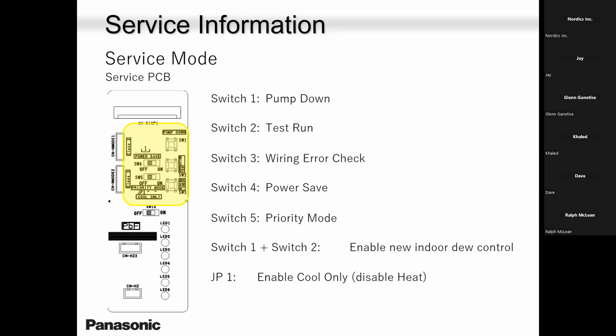Never put the unit in heat mode and say, oh, it's heating well, but there is something wrong. The best way to test the equipment and troubleshoot is to put it in cool mode. Even if it's cold outside, it doesn't matter. The easiest way to me, as far as I'm concerned, I like to troubleshoot these units in cooling. It gives me an answer in almost less than 10 minutes. So that's the way I use this test run in a multi-zone.